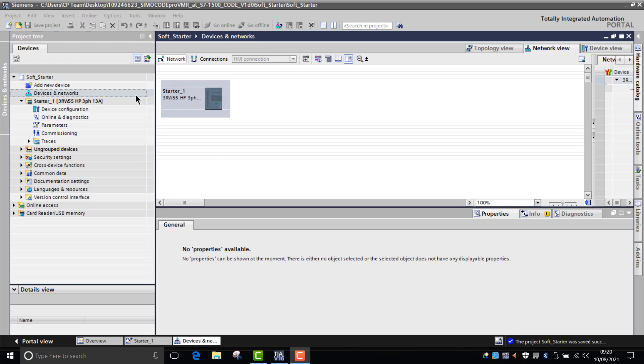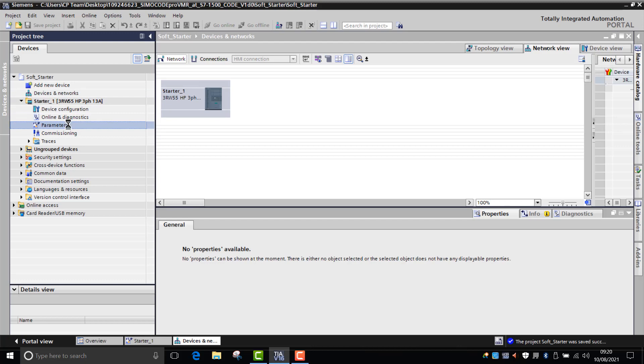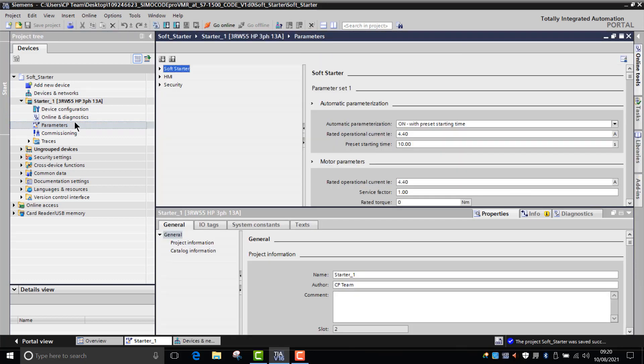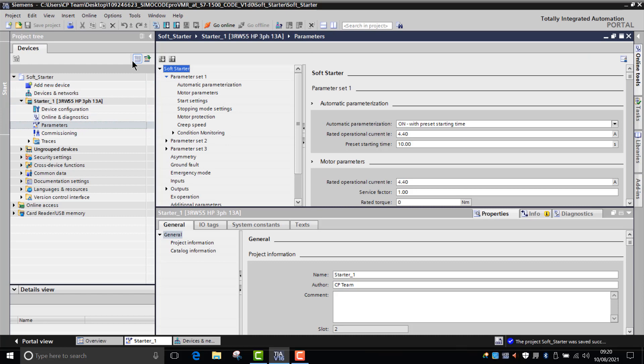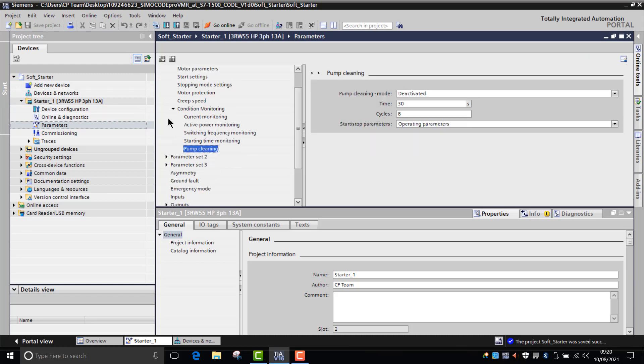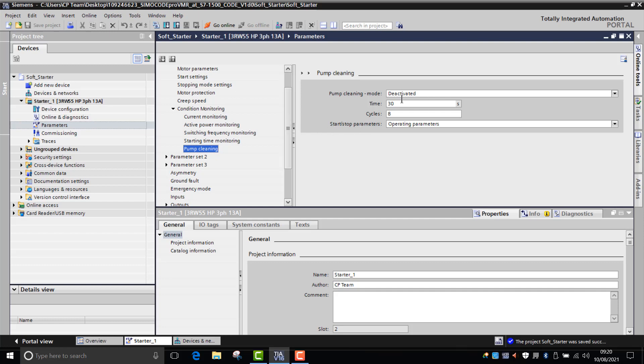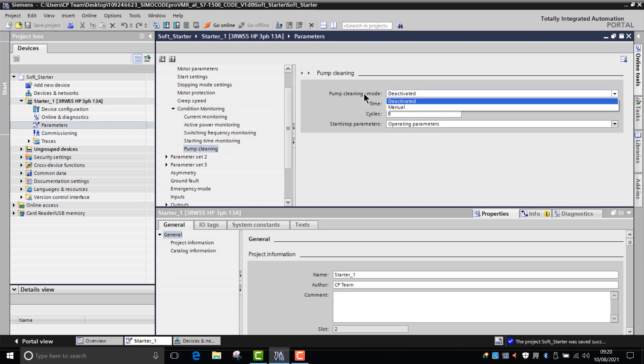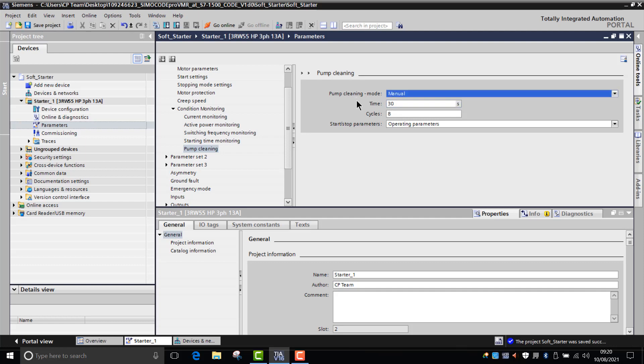So how does it work? If we go into the parameters and then from parameters, go into parameter set one, go into condition monitoring and drop that pump cleaning function down. As you can see at the moment it's deactivated. How do we gain access to it? Well, all we have to do is go into the pump cleaning mode function and click on manual mode. Once you've done that, this function will then be active.